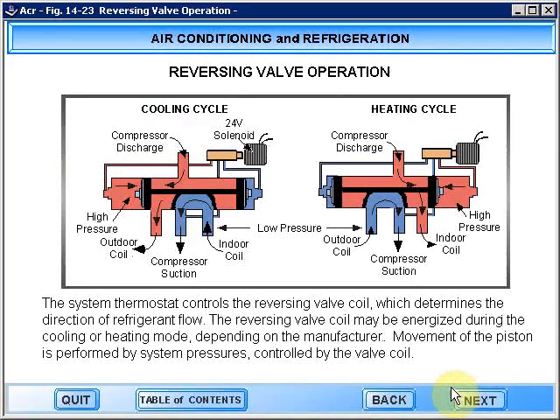The system thermostat controls the reversing valve coil, which determines the direction of refrigerant flow. The reversing valve coil may be energized during the cooling or heating mode, depending on the manufacturer. Movement of the piston is performed by system pressures controlled by the valve coil.